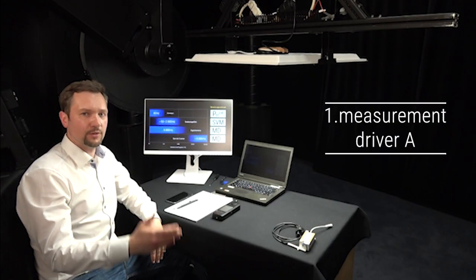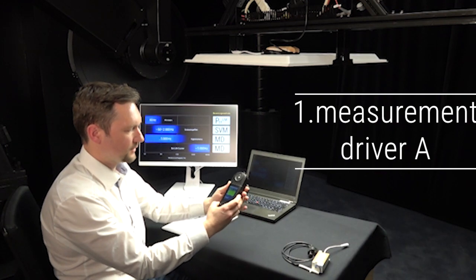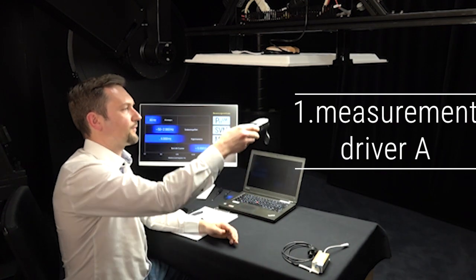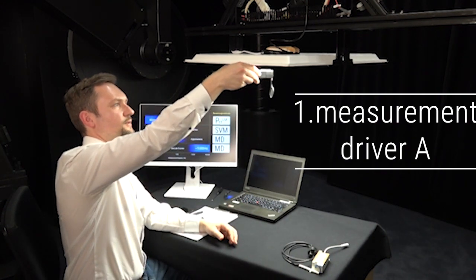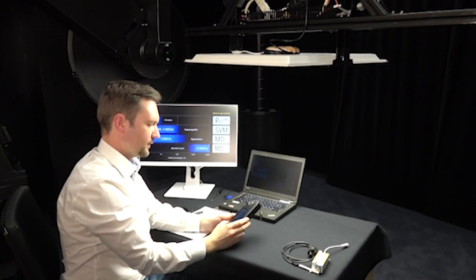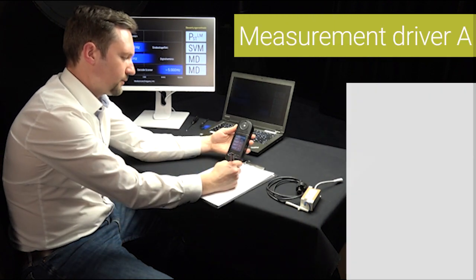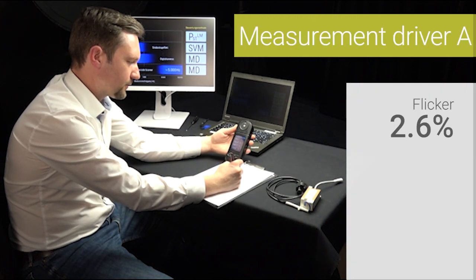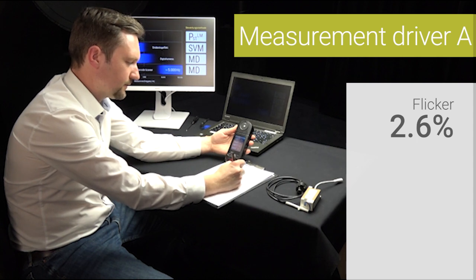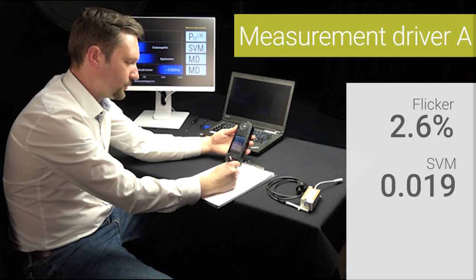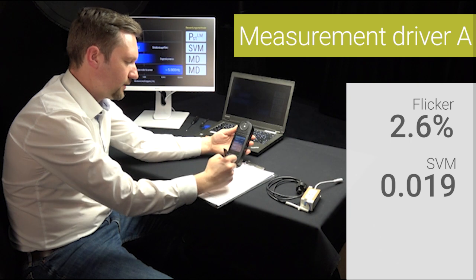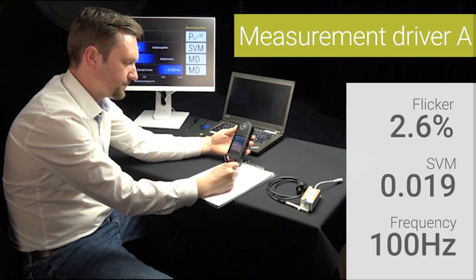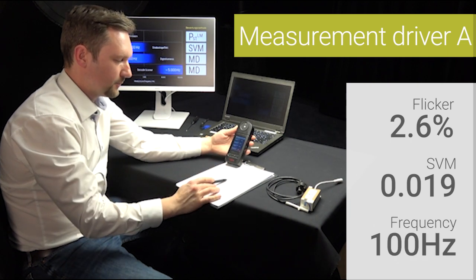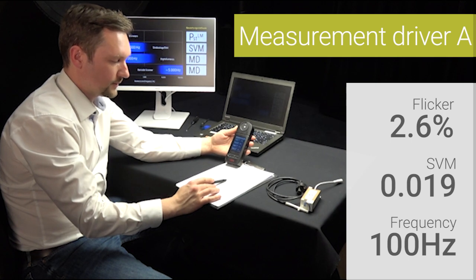Now the luminaire is in operation, and the measuring device is already running. We are getting very close to the luminaire and record the data. For driver A: flicker of 2.6%, SVM of 0.019, frequency at 100 Hz. The PSTLM information was already taken from the driver's datasheet.